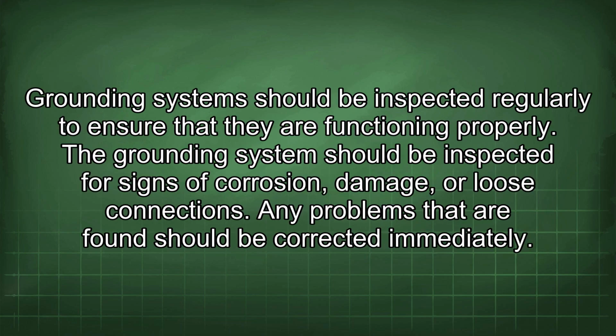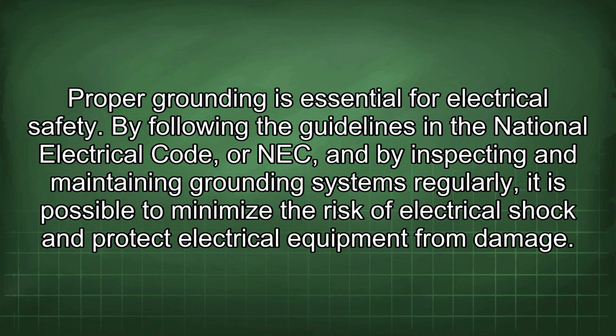Grounding systems should be inspected regularly to ensure that they are functioning properly. The grounding system should be inspected for signs of corrosion, damage, or loose connections. Any problems that are found should be corrected immediately. Proper grounding is essential for electrical safety. By following the guidelines in the National Electrical Code, or NEC, and by inspecting and maintaining grounding systems regularly, it is possible to minimize the risk of electrical shock and protect electrical equipment from damage.